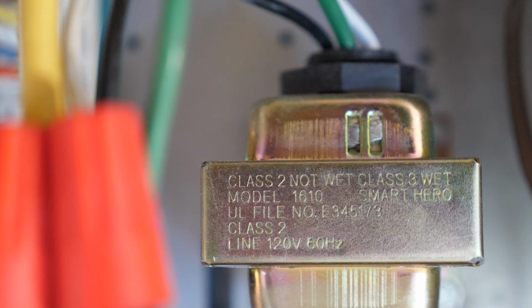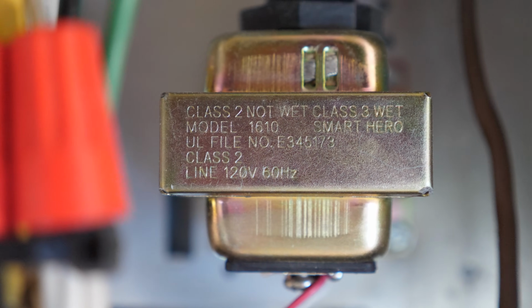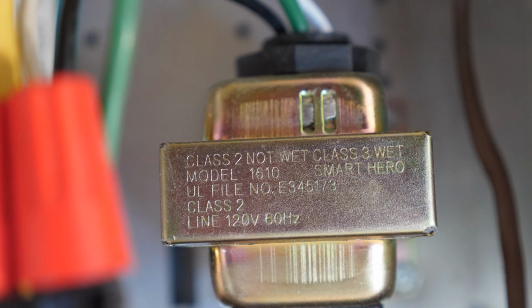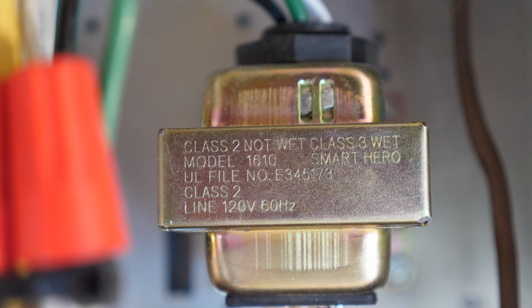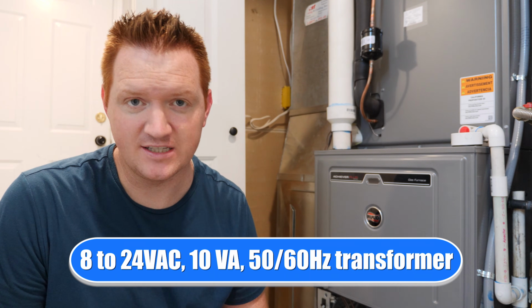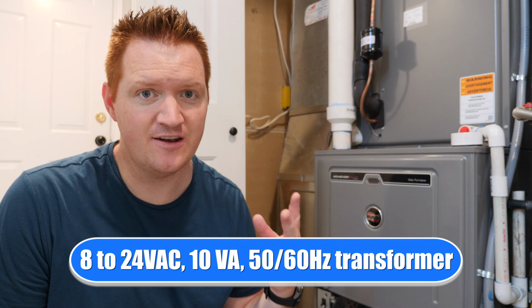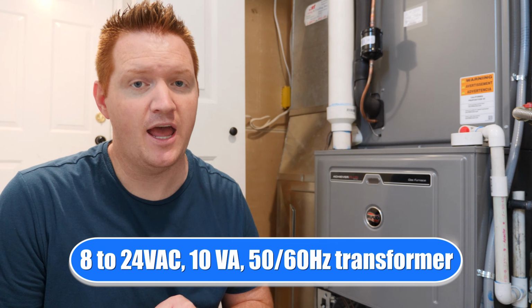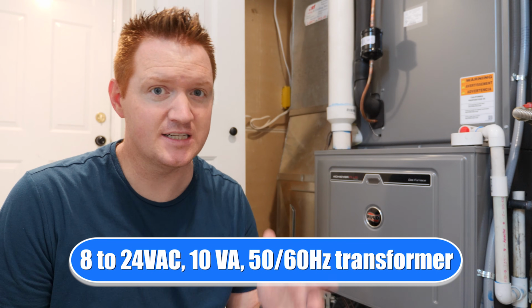Now here on the transformer, I don't actually see what the voltage is. I do see a model number and I could Google it, but down here we have 120 volts, 60 hertz. That's good news because the Nest Doorbell requires not only 8 to 24 VAC, but also 10 VA, volts amperage, and 50 to 60 hertz.